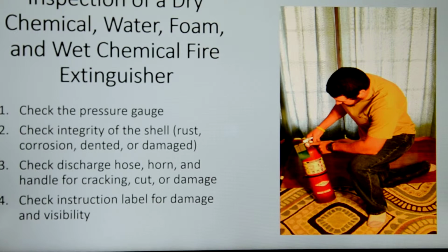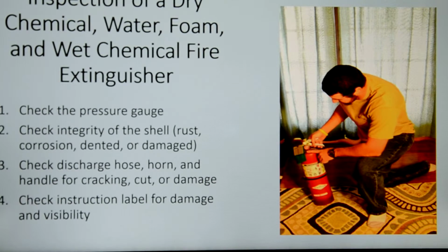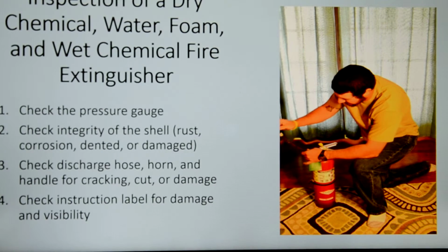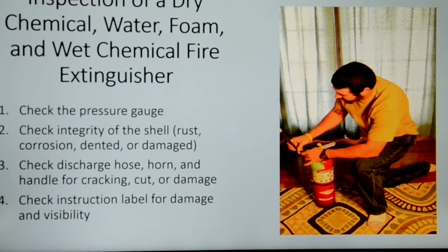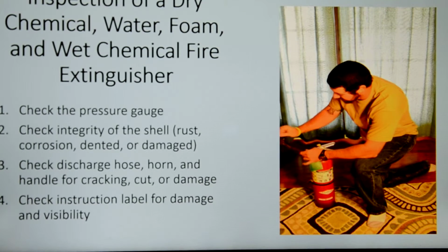Then you want to check the gauge. Make sure it's in the green, not the red. Make sure it's good to go, fully charged. Then you want to check the hose and the horn. Make sure neither one of them is cut, cracked, corroded, all good, no dry rots.